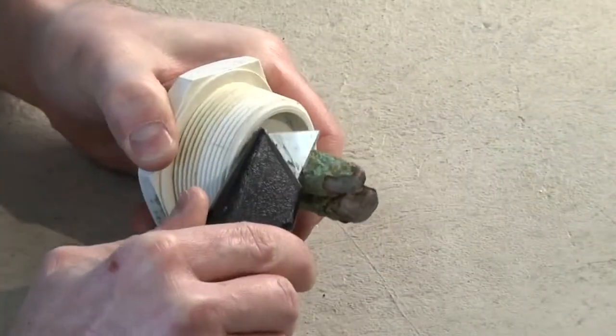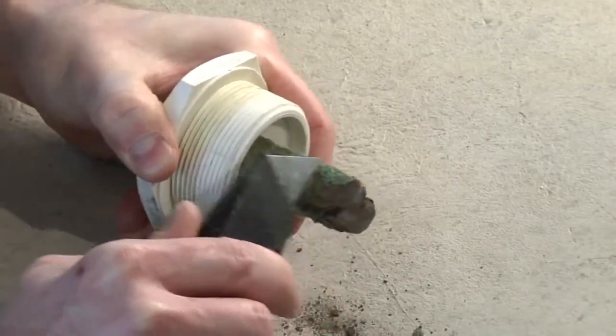The scale can be easily brushed or scraped off the bars, which will improve the probe's performance. The IonGen does contain a built-in self-cleaning mechanism for the probe, but it does require sufficient water flow to work properly. If you repeatedly notice scale building up on the probe, then you may want to move the probe to an area of better water flow.